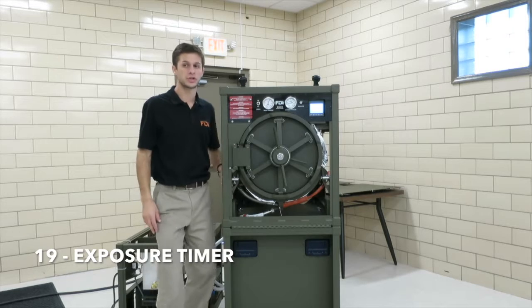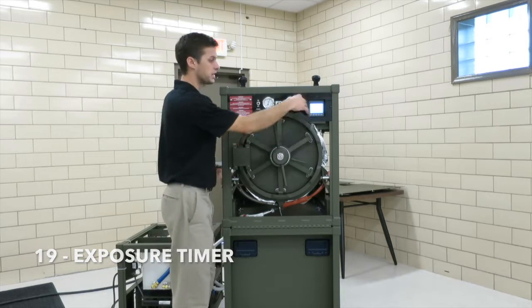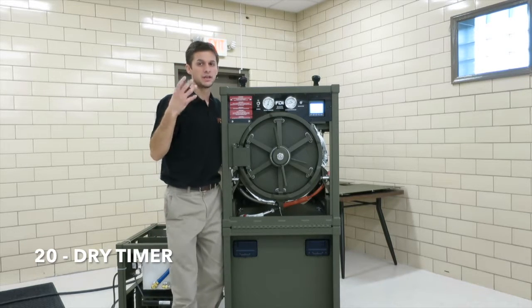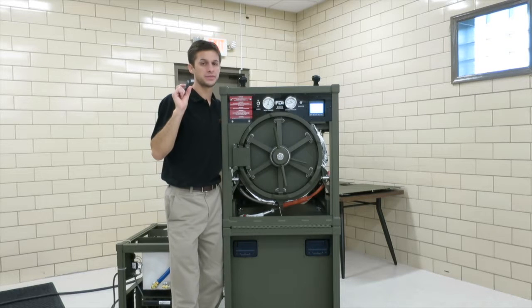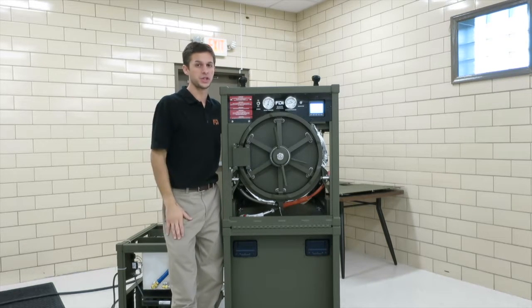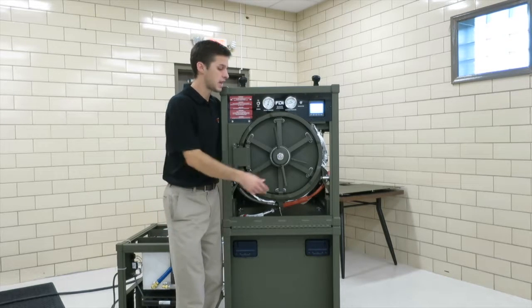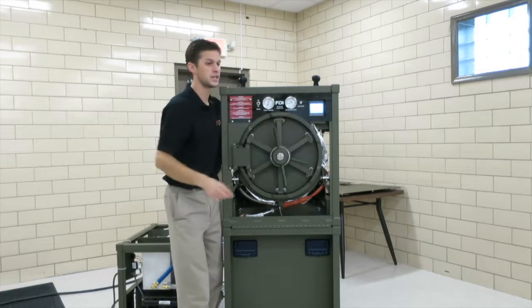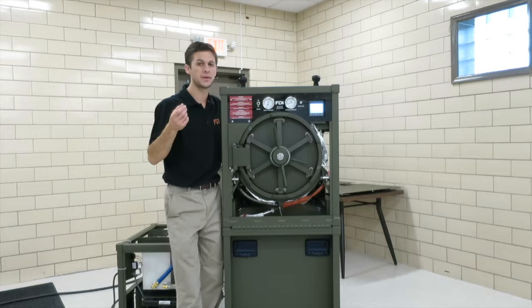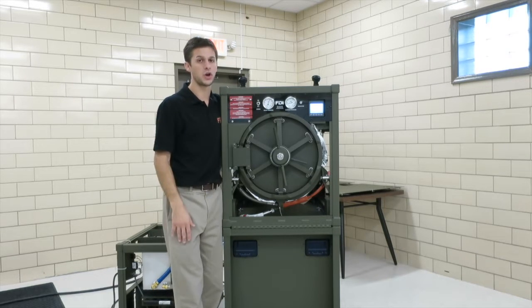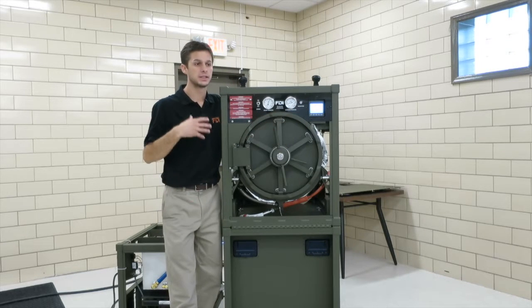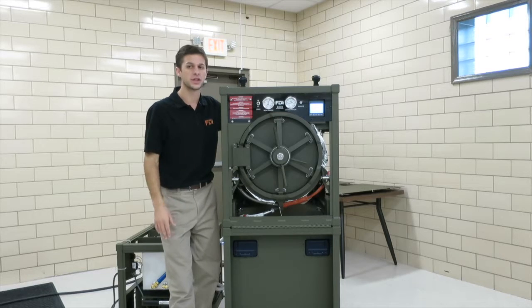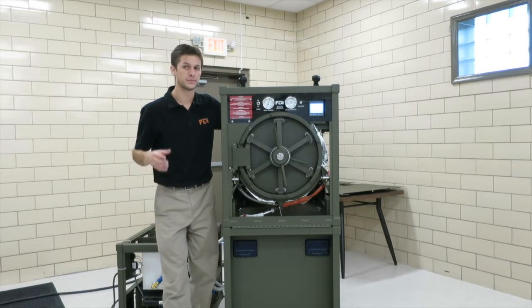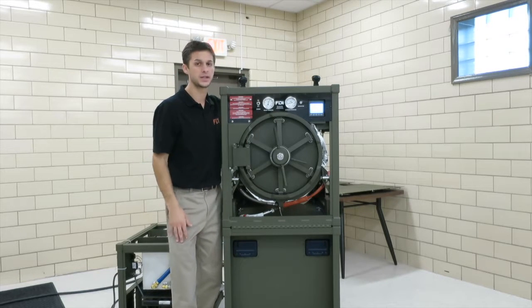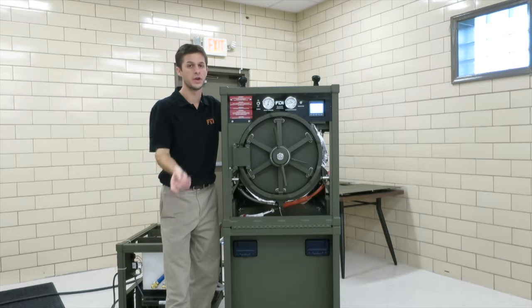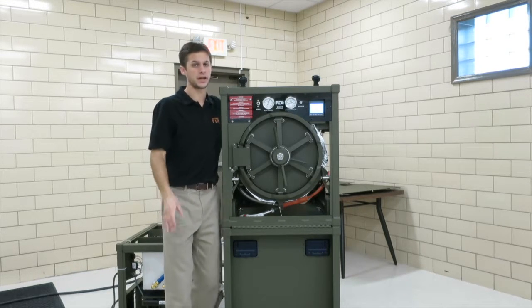So number 19 is exposure timer, and number 20 is dry timer. Both of these are watchdog timers saying the exposure should take this amount of time and the dry should take this amount of time, within a little bit of a cushion. If either one of those is out of tolerance, there's a battery in this PLC that operates the real-time clock. If the real-time clock is going slower than normal, you could get these alarms. That battery is supposed to last 5 years. If it's running out, running sluggishly, you may get one of these alarms, 19 or 20, and you'll know that the real-time clock is not as accurate as it once was. So you'll have to follow the battery replacement procedure that's in the back of the manual.